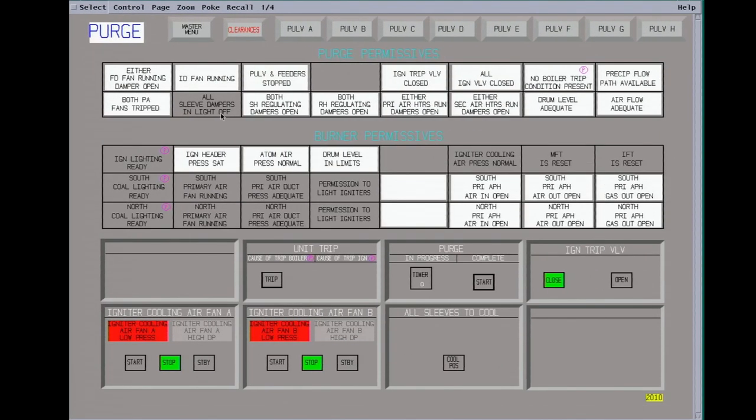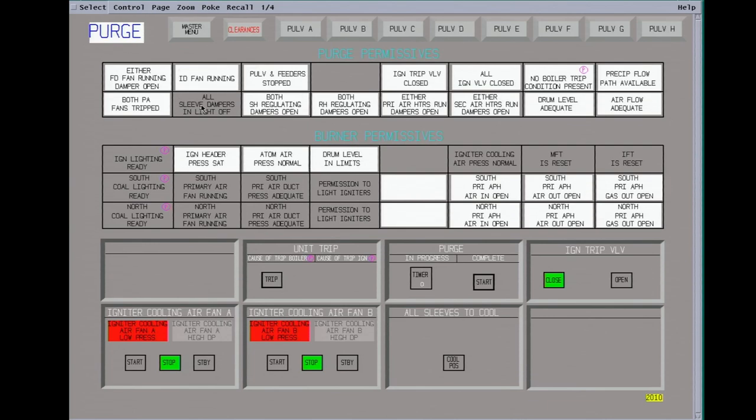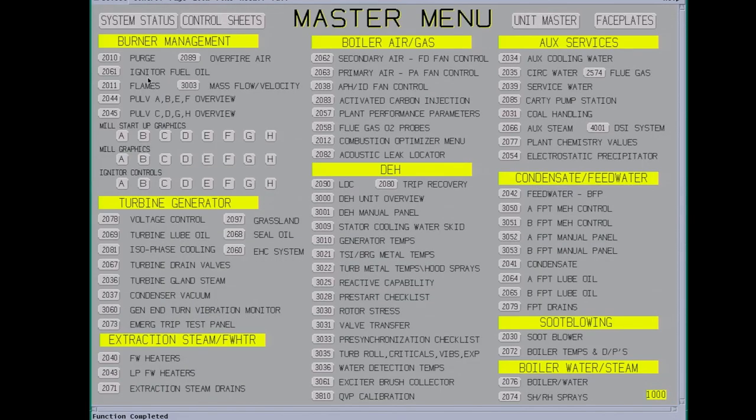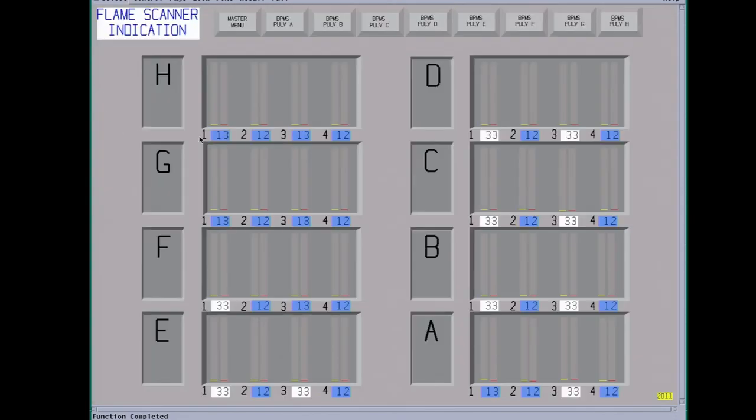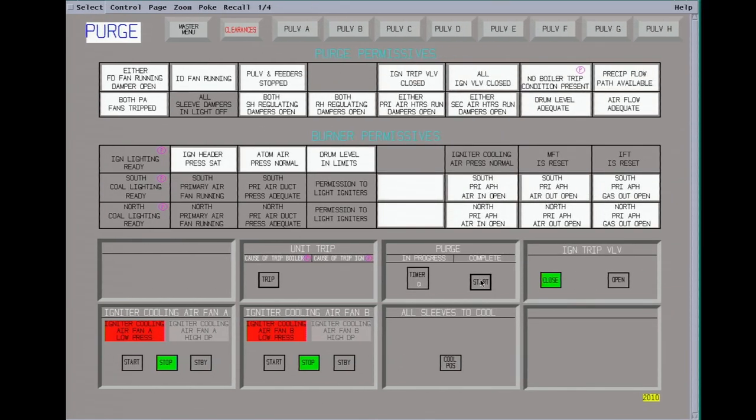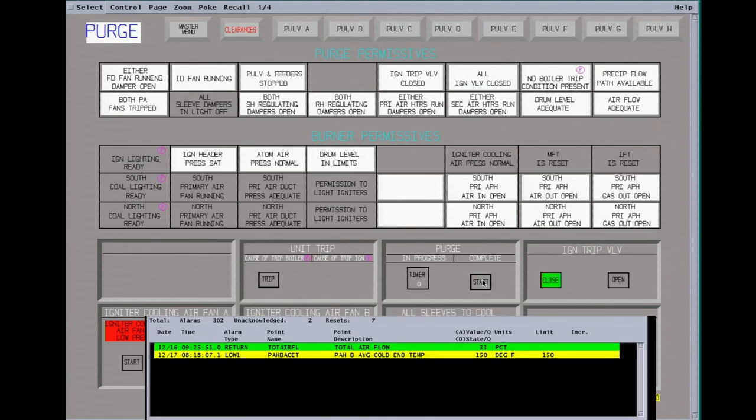Okay, on our purge permissive screen, we have all these made up. The only thing we're missing are the sleeve dampers. The sleeve dampers, every burner has a sleeve damper. The purpose is to control the amount of air feeding in that individual burner. Here's the boiler layout. On one side you have four decks of burners, four burners a piece. It's on the front and the back side. This is the sleeve damper position. They have to go to the light off position. That way it will allow enough air through the furnace to ensure you have a good purge. There have been some nice changes made. We can go to the start and it should move all the sleeve dampers. Otherwise you have to move them manually. It takes a little bit of time.